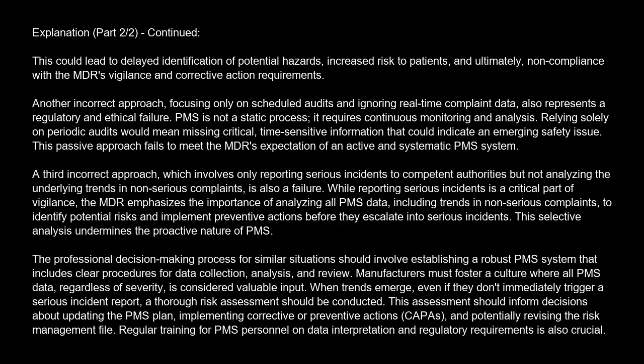A third incorrect approach, which involves only reporting serious incidents to competent authorities, but not analyzing the underlying trends in non-serious complaints, is also a failure. While reporting serious incidents is a critical part of vigilance, the MDR emphasizes the importance of analyzing all PMS data, including trends in non-serious complaints, to identify potential risks and implement preventive actions before they escalate into serious incidents.